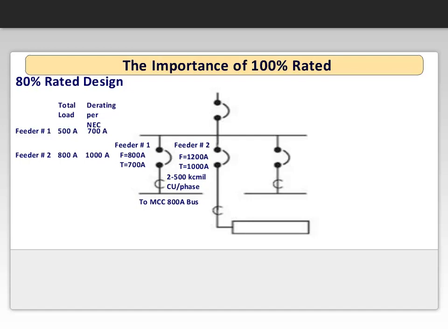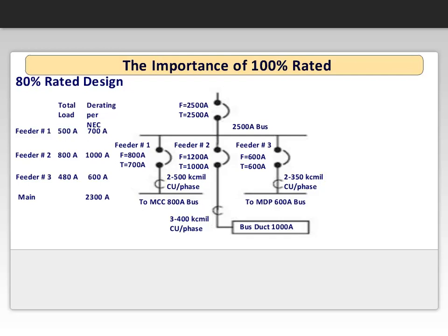The cable will be sized with 3 400 kcmil copper cables per phase, and our busway would need to be sized for 1000 amps. Feeder number 3 is providing power to a main distribution panel with a 480 amp load. After derating it, we wind up with a 600 amp breaker and a 600 amp trip. The cable feed is two 350 kcmil coppers per phase. As a result, the main breaker must be sized at 2500 amps with a 2500 amp trip.